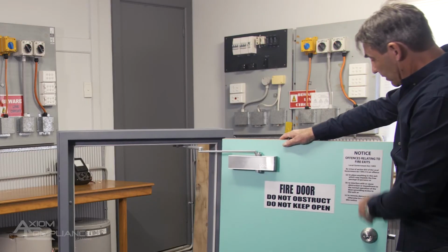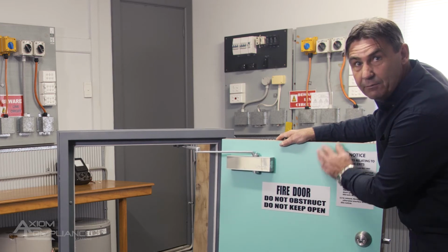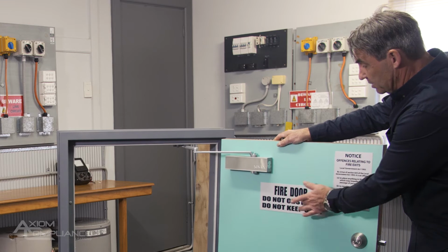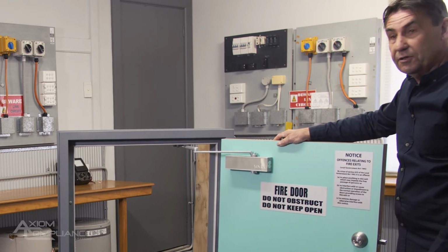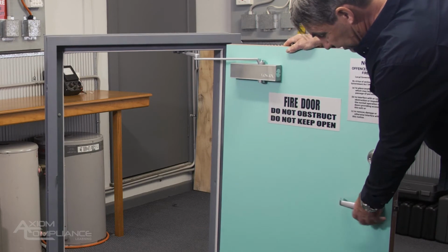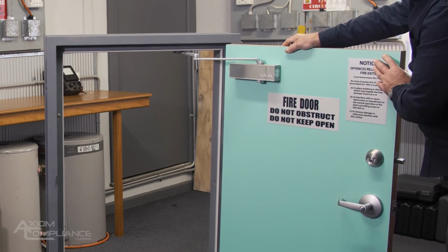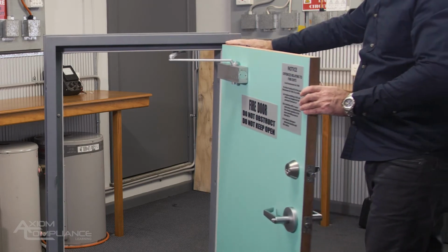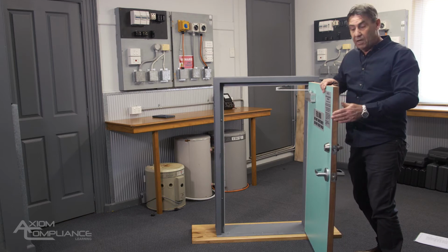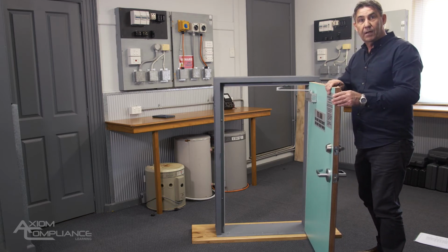So now that we've got the door open, we can see the other side of the door, and we can see the other side of the door is just laminated with masonite, so we can't see the inside of the door. But we can see our signage, and we can see that we have the appropriate signage on this side of the door as well, and our lock set looks fairly tight and good. And it doesn't look like we've had any damage to the door as well. So while we've got our door open and we're checking it out, and this is a part of the checklist, make sure that you don't have any damage to the door, okay?